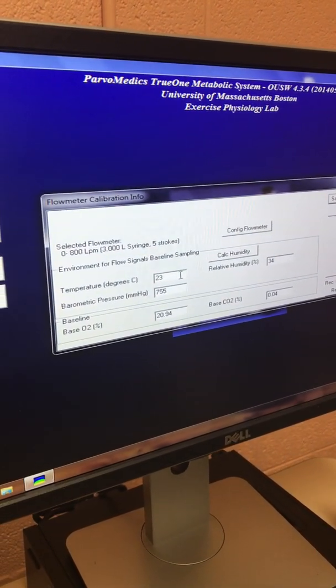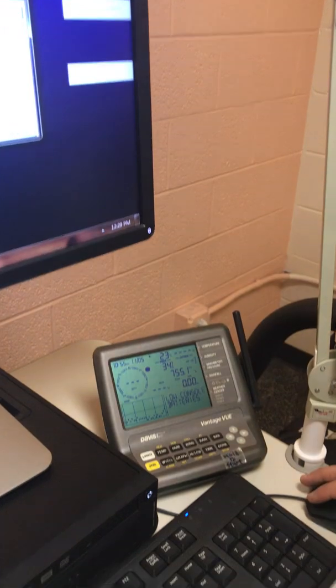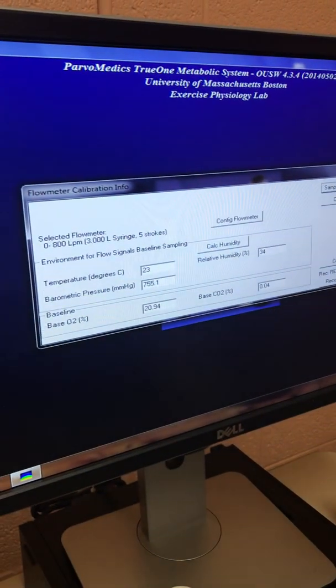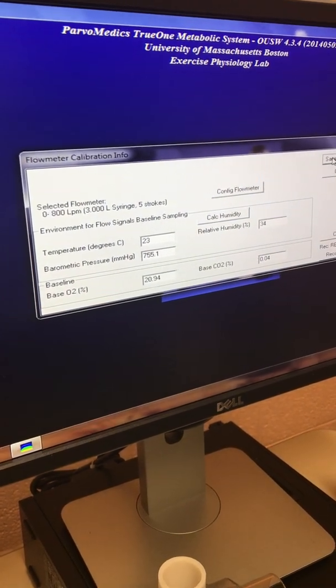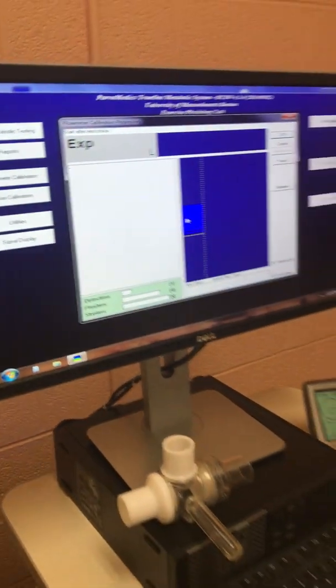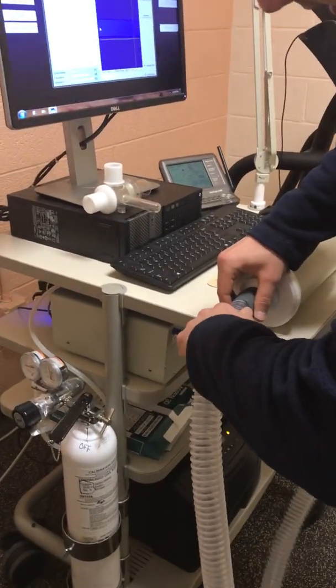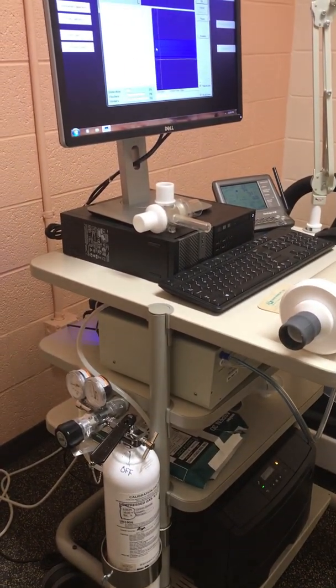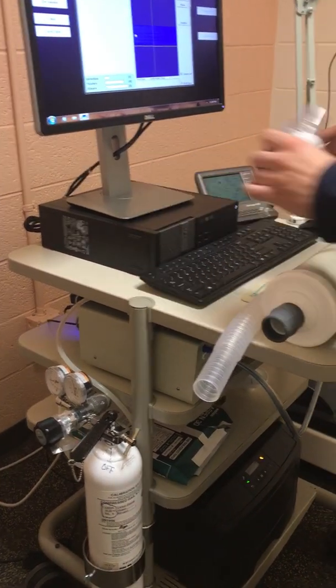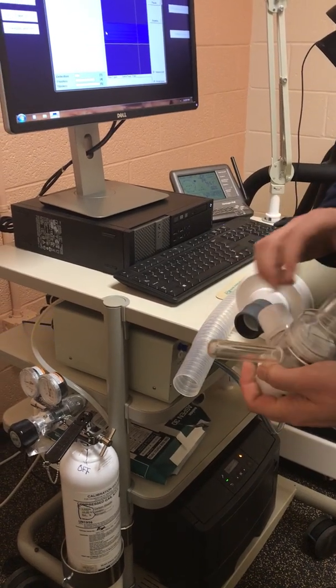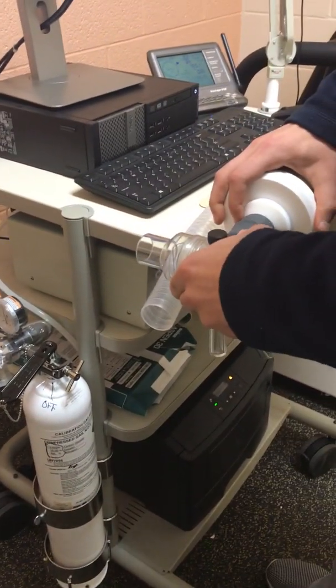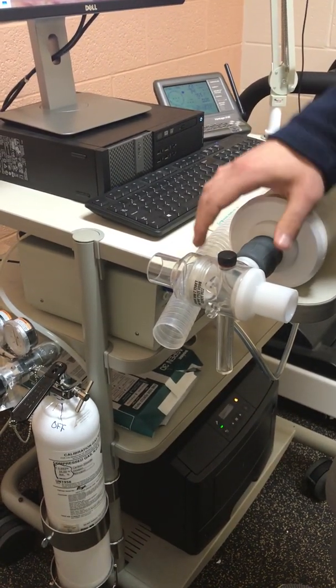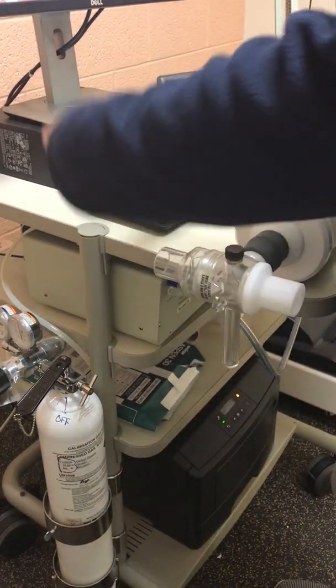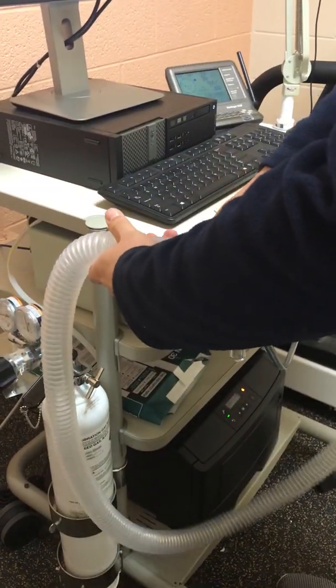And once again, we're going to look at our environmental conditions: 23 degrees Celsius, 34% humidity, and we have 755.1 millimeters of mercury for barometric pressure. So that looks good. And so now we're going to do our flow meter calibration, and this is to establish a connection between our ventilation, and that actually doesn't go in that hole. We're going to put the mouthpiece here, and so this is going to replicate the subject actually having this mouthpiece while they're performing a test, and we're going to collect the expired gases out of this side of the face mask.